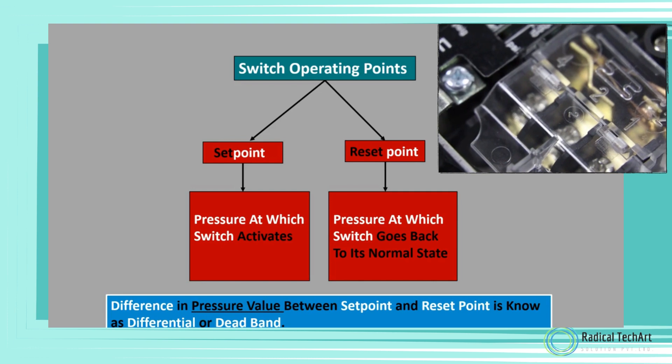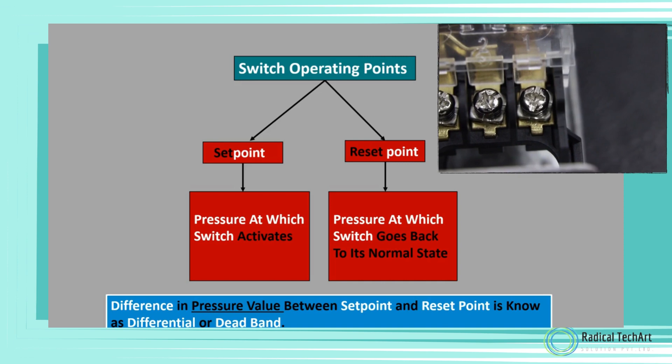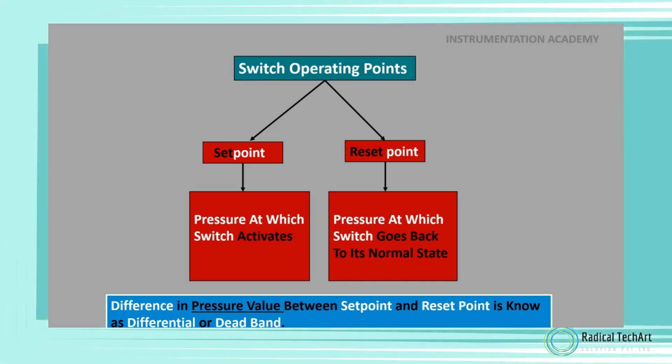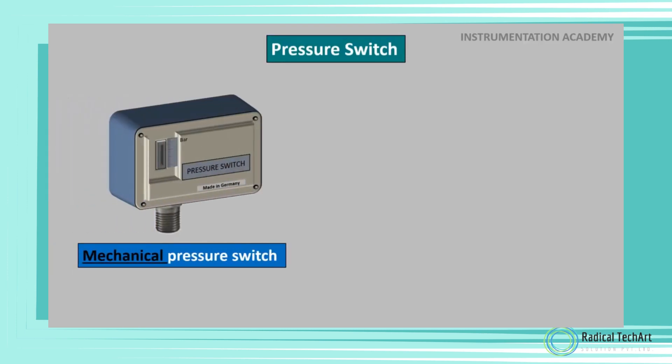The difference in pressure value between the setpoint and the resetpoint is known as differential or dead band of a pressure switch. In most switches, differential can be adjusted, and some switches have fixed and not adjustable differential.